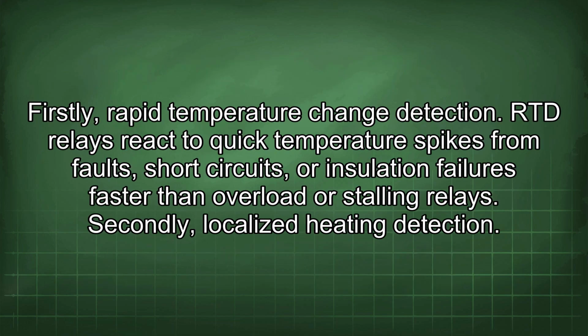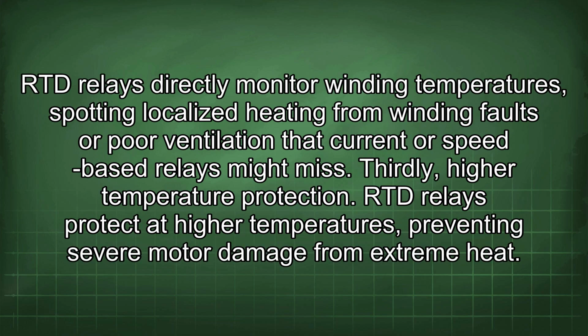Firstly, rapid temperature change detection. RTD relays react to quick temperature spikes from faults, short circuits, or insulation failures faster than overload or stalling relays. Secondly, localized heating detection. RTD relays directly monitor winding temperatures, spotting localized heating from winding faults or poor ventilation that current or speed-based relays might miss.